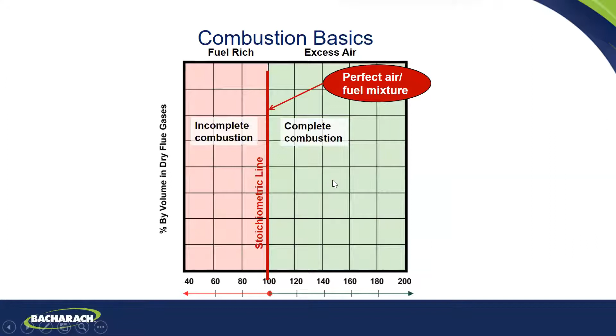So oxygen's only going to be on the excess air side in the stack as we add that excess air, which is oxygen, into the combustion process. Okay, so we're going to start adding. The more we add, the higher the oxygen concentration, the more our excess air number is, and the lower our CO2 number is. CO2 is diluted by oxygen and has a direct relationship on the excess air side.